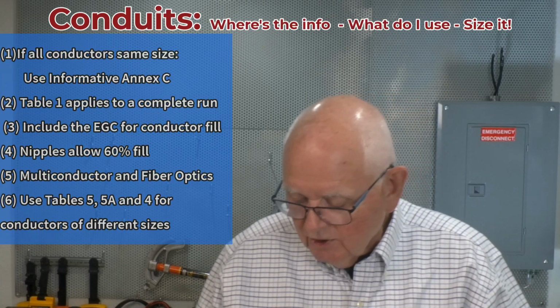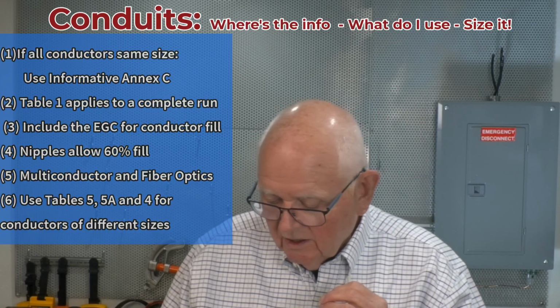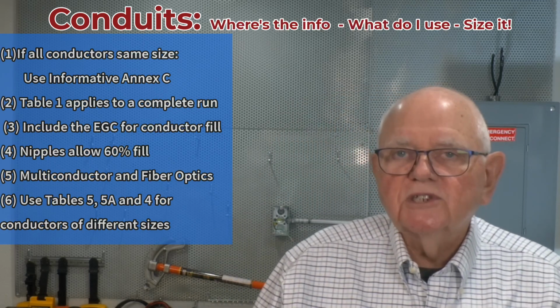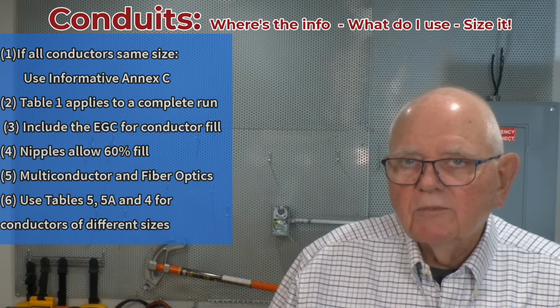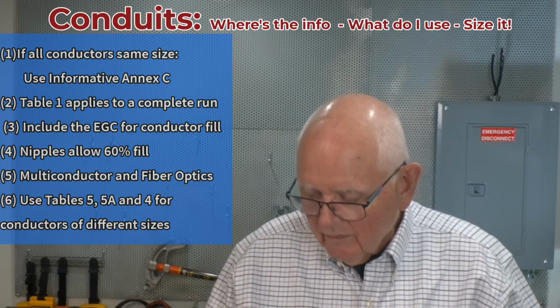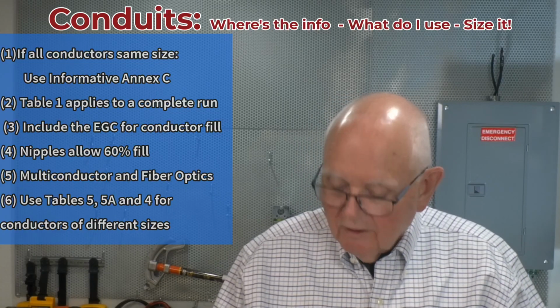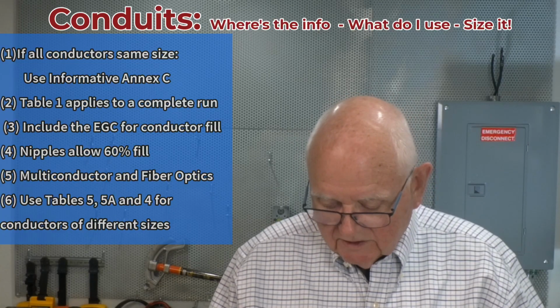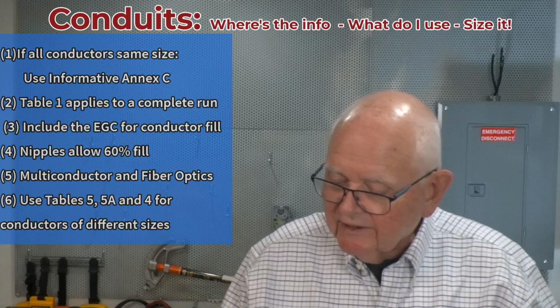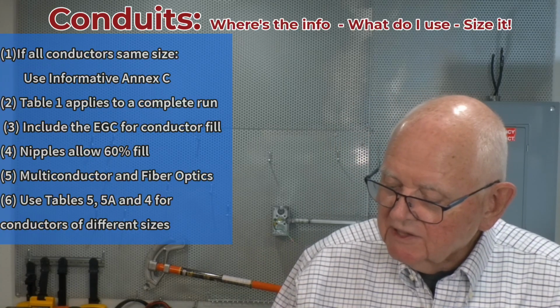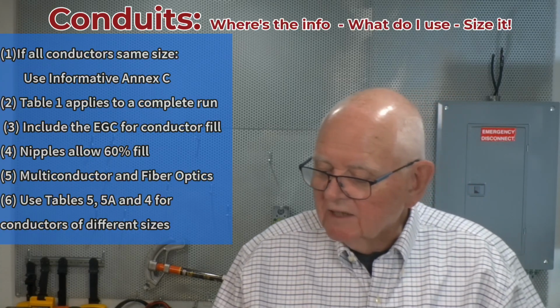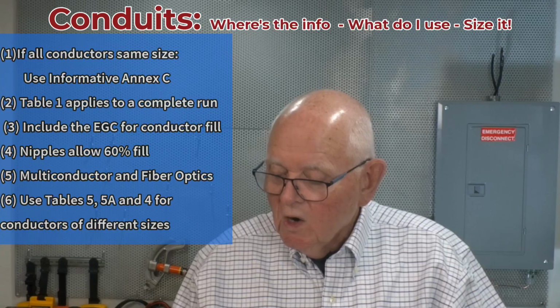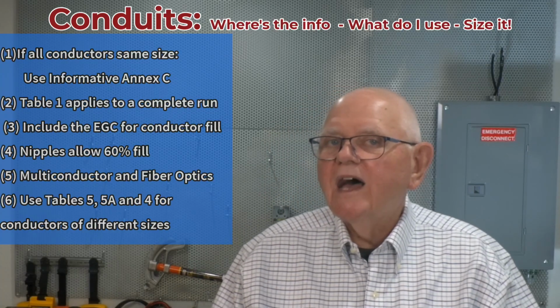Where conduit or tubing or nipples not exceeding 24 inches, there's my 60% fill for nipples in note number 4. Note number 5 talks about multiconductor cables. Note number 6, for combinations of conductors of different sizes, oh, we're going to have to go to Tables 5 and 4.